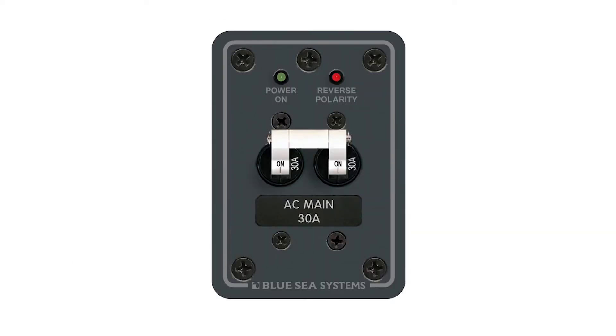When we have an alternating current system — 120V, 220V, whatever it is aboard a boat — at the main panel there should be, and most of us have, a little light generally labeled 'reverse polarity,' and it's generally red. That little red light measures voltage between the neutral, called the grounded conductor, and the AC ground, called the grounding conductor. In all circumstances it should really be zero if things are working perfectly, because your ground and neutral should always be at the same potential with no voltage differential between the two.